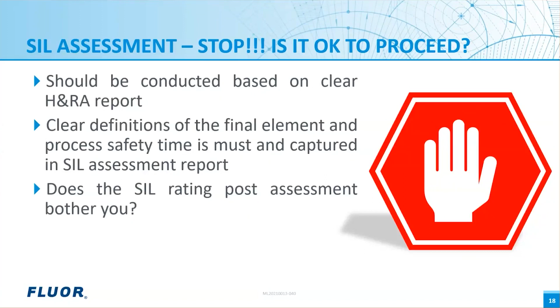Basically, the process safety time is the time you have, or the SIF has to respond, so that it could prevent the unwanted event. As Amit mentioned, the SIF has to respond faster than the process safety time. The process safety time is derived from the process design itself and the process conditions it's operating under. That's why it's important for us to know the process safety time, so that SIF designers know how fast their SIF should respond to prevent the unwanted event.